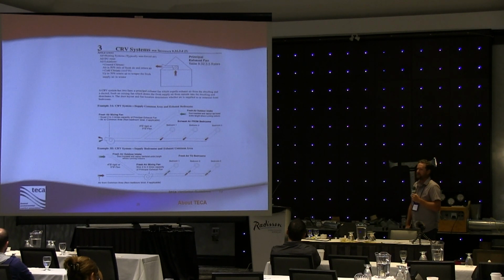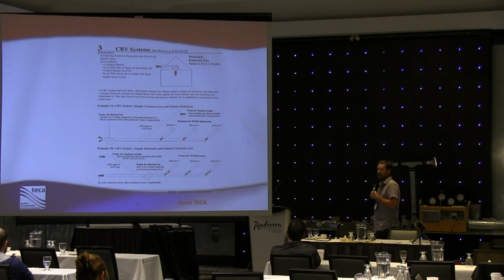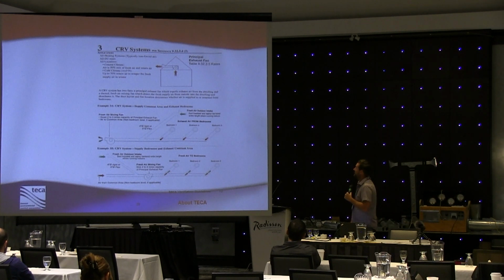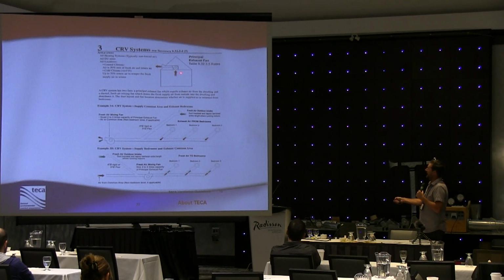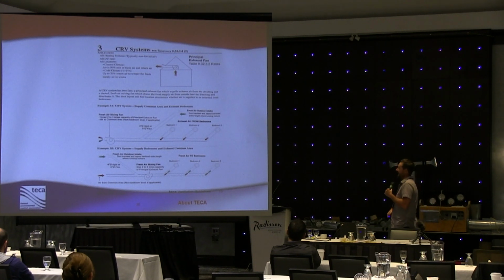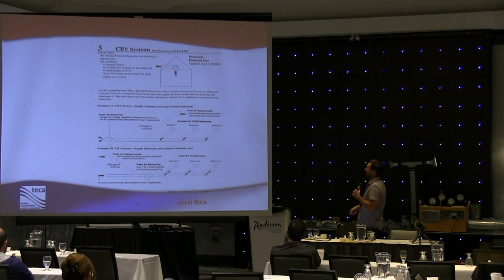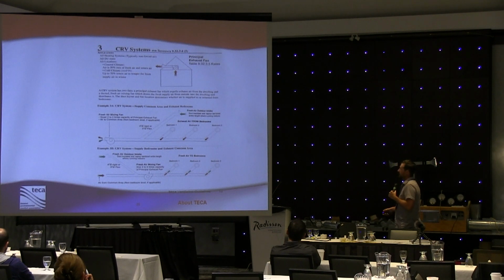A system like this is not without its downfalls. Again, we are exhausting conditioned air directly to the outside, so we have an energy loss there that we could avoid if we did a different type of system. However, this does work fairly well. This fan has to run continuously also, so there is an energy impact with running that fan. We've got some electrical consumption, and we also have a lot of electrical consumption with this fresh air mixing fan.